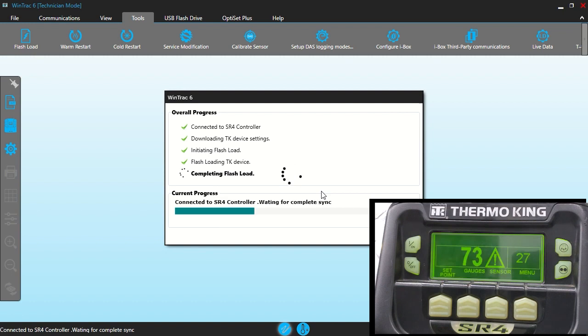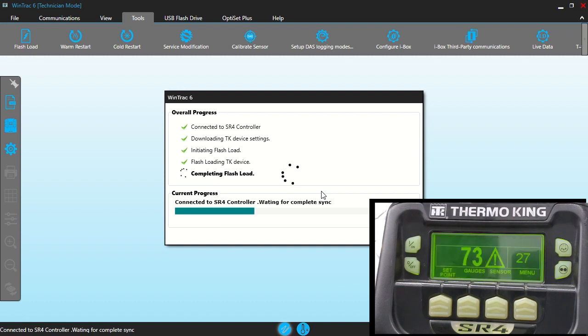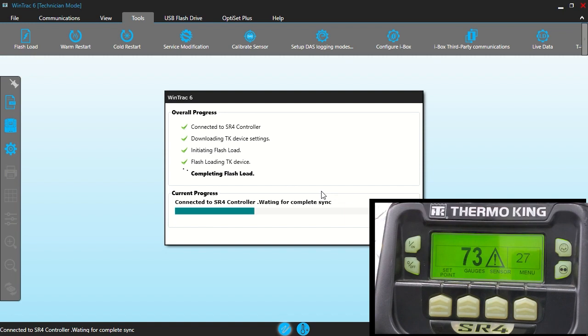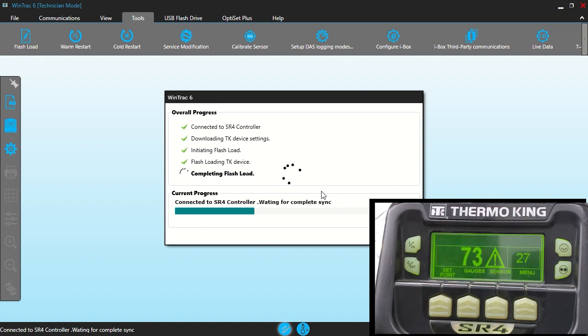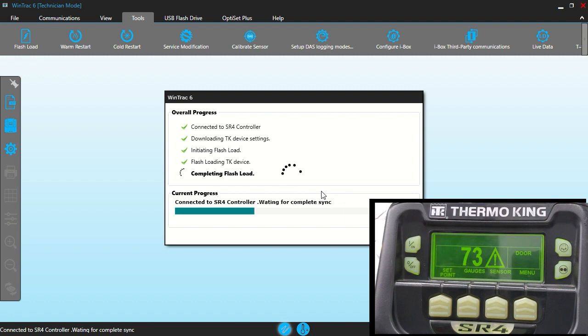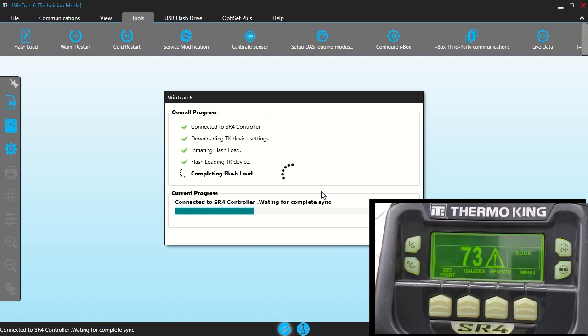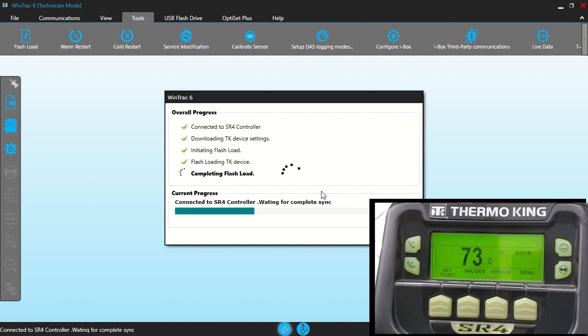I pulled the high pressure cutout on this. You'll notice that it's flashing with a shutdown alarm. I pulled the high pressure cutout because with the last version of software on it, it wanted to start. So I wanted to keep it from starting. That was what I knew would work for sure the first time.